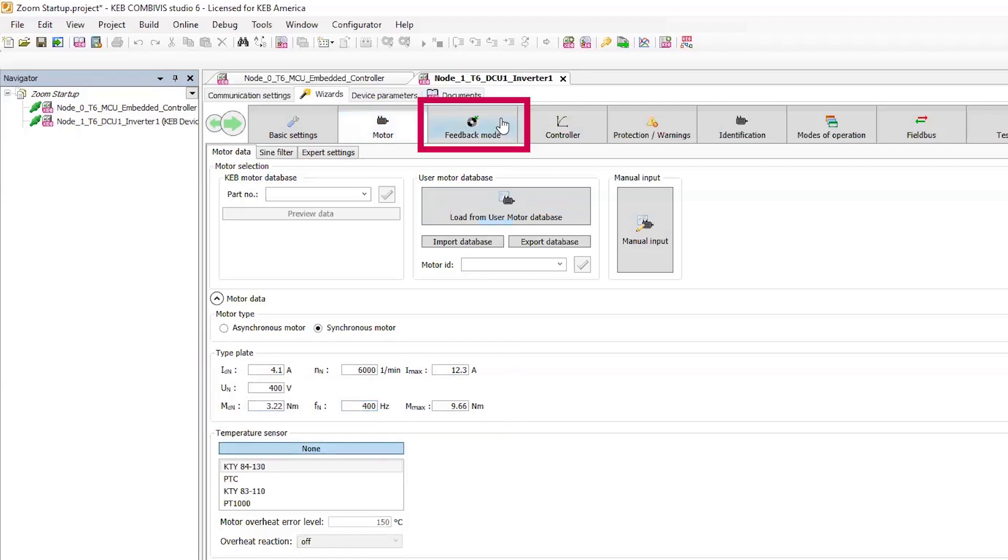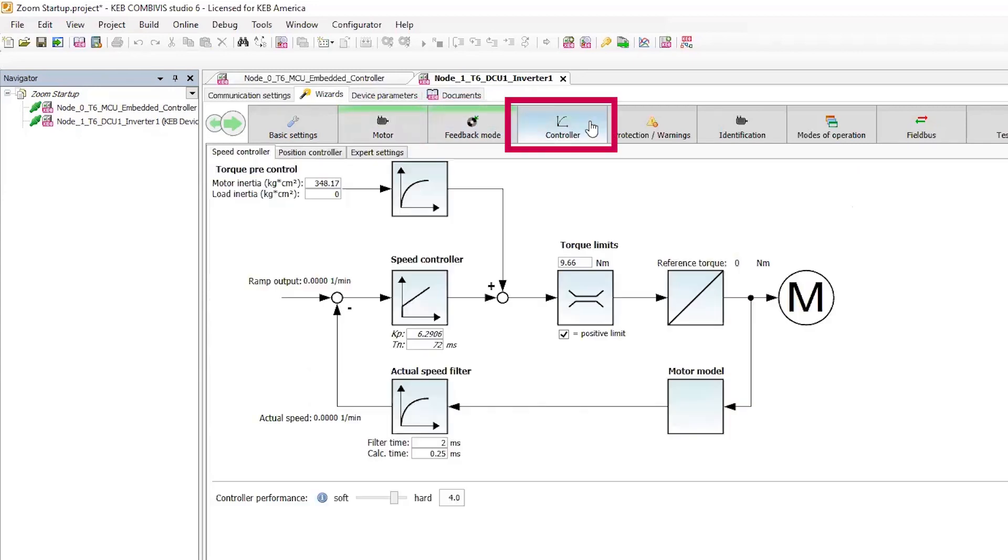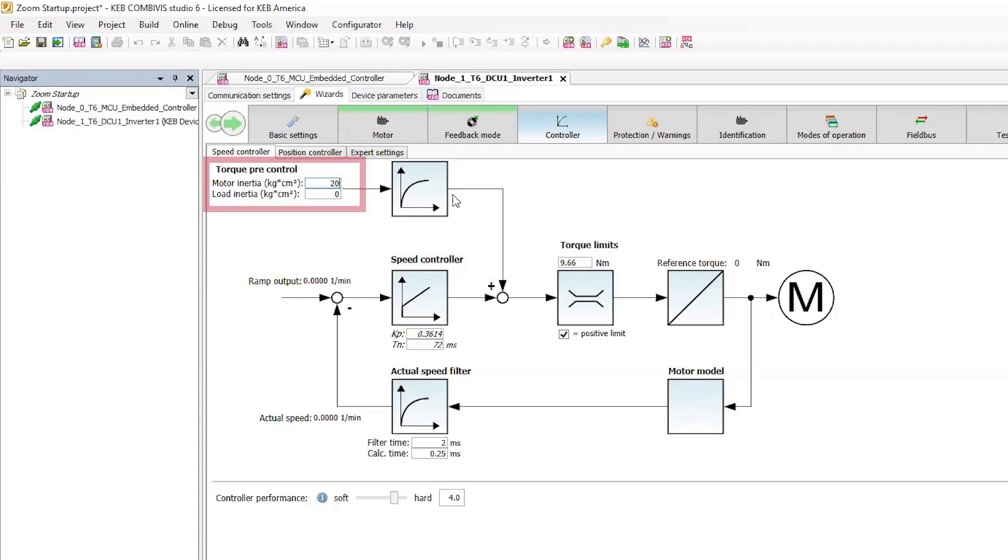Then in the feedback mode tab, I'll ensure that encoder is selected. Then in controller data tab, I'll put in a nominal value for the inertia value. This pre-calibrates the speed control PI loop.